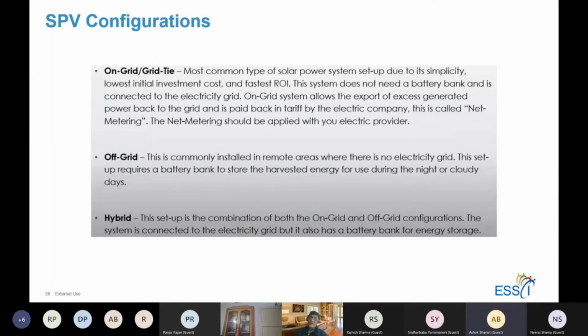This is because it must have what is called anti-islanding capability. It cannot be an island of power generation on its own into the grid, because if the net is shut down by the distribution company, it could be for conducting some repair. And if there are islands of power generation on it, it can electrocute the electrician who is working on the grid. So a grid tie system will work only if there is power from the grid.